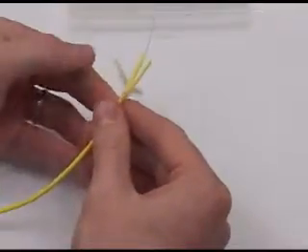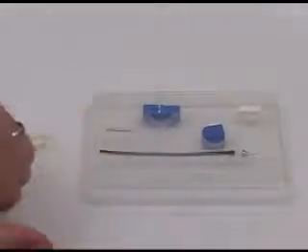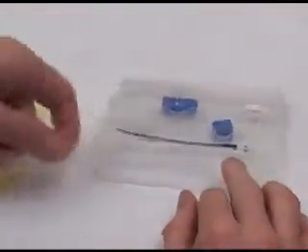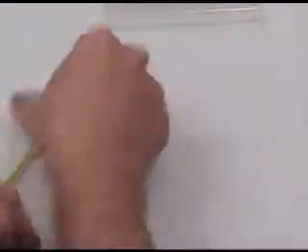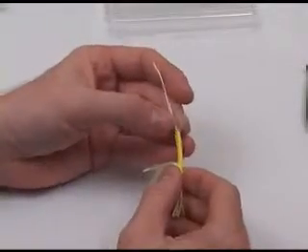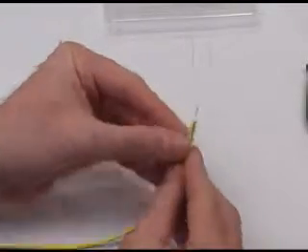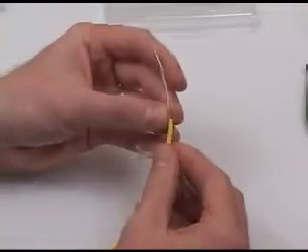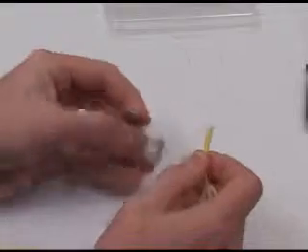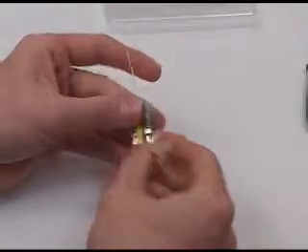Now return back to the packaged parts and remove the protection sleeve. Insert it over the 900 micron jacketing down into the base of the 3mm cordage slit. Now with the protective splice sleeve in place, load the cordage in the cordage holder. Close the cordage holder and prepare for final stripping.